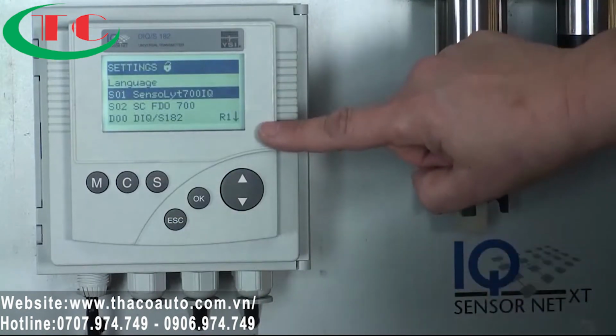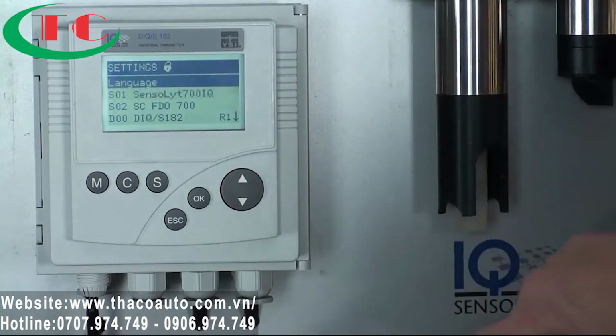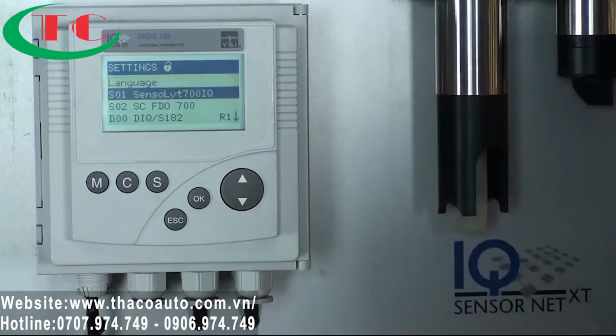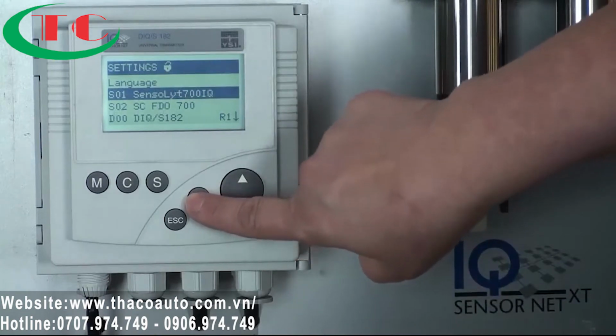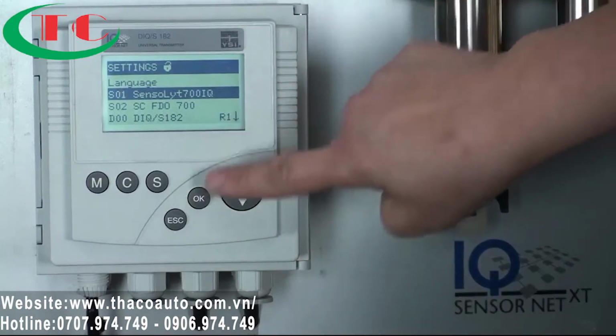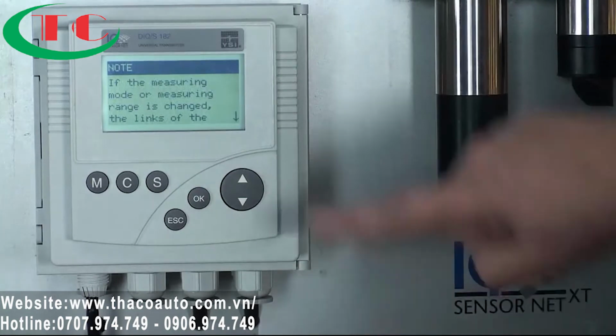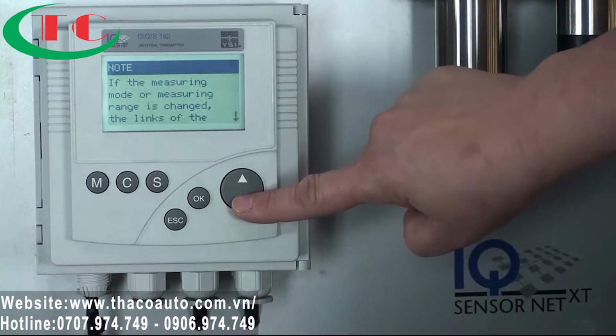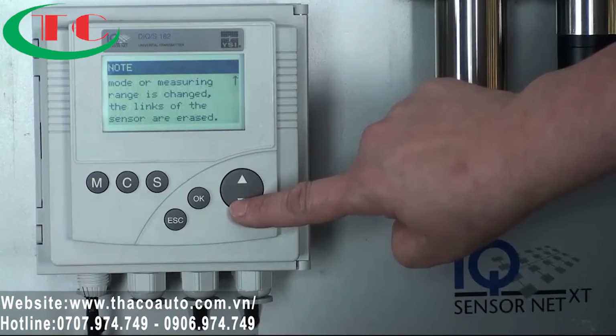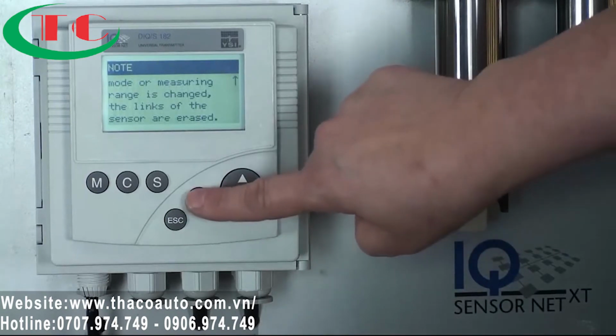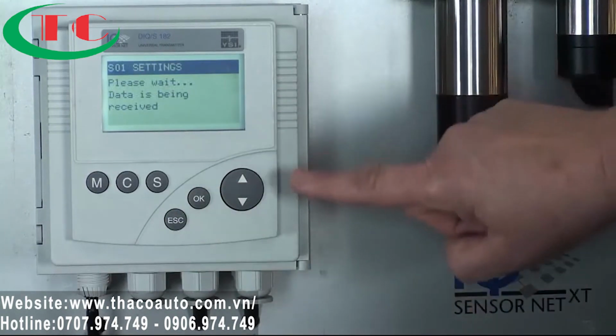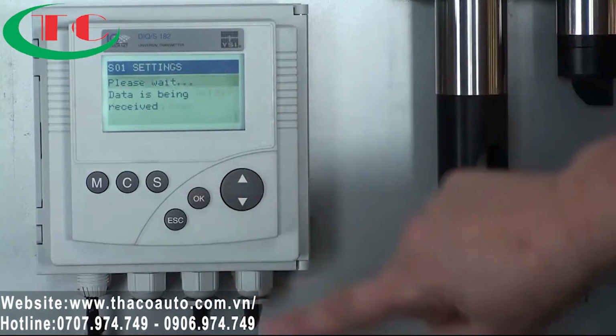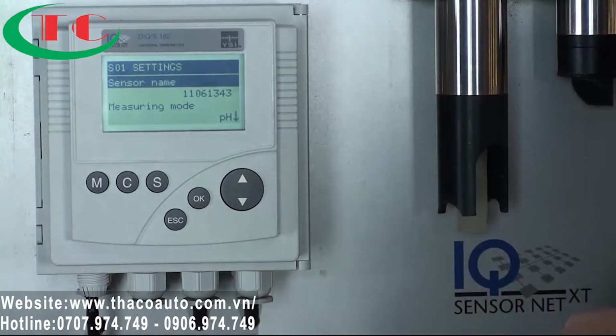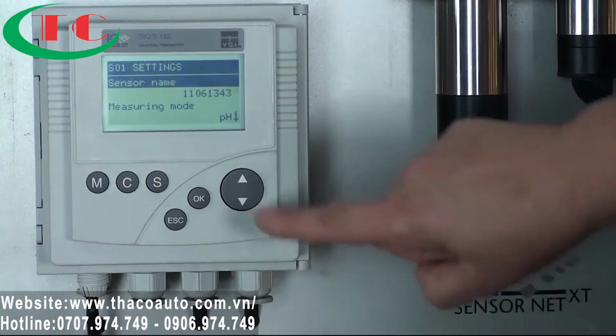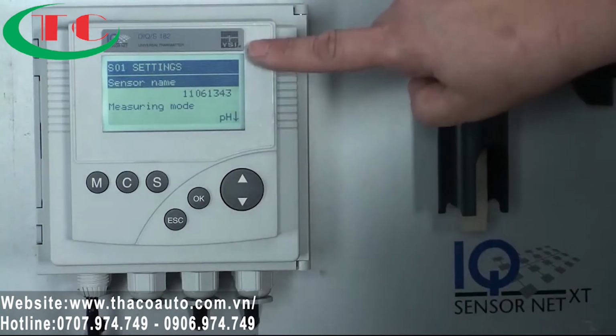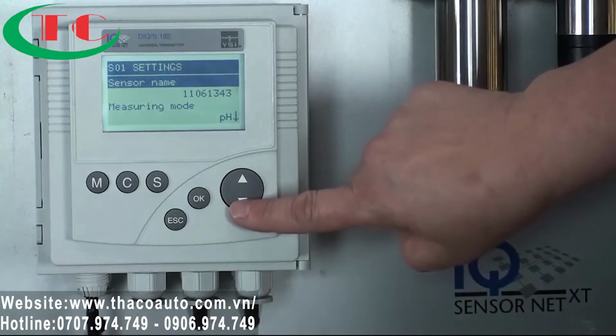The S button takes us to the settings. We can choose a language. We can get into each one of the sensors. In this case, I'm going to look at sensor 1, which is the SensoLyt 700 IQ. If I press OK, it's going to give me this warning: if the measuring mode or measuring range is changed, the links of the sensors are erased. We don't have anything linked, so I'm going to go ahead and press OK. Even if I did have something linked, as long as I didn't change the measuring mode or the measuring range, everything would be fine. And this is where you can get into the settings of your individual sensors.